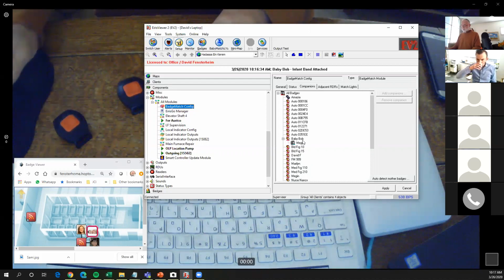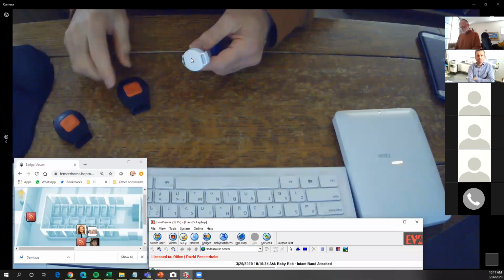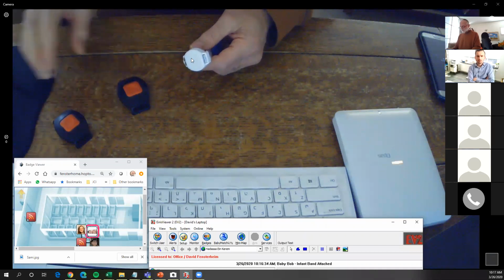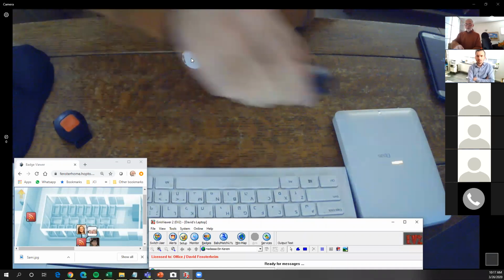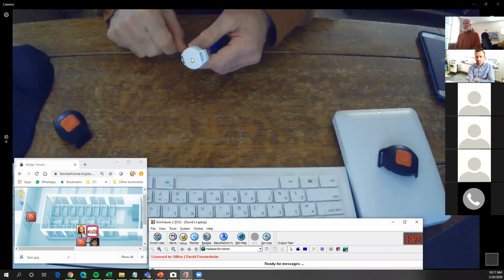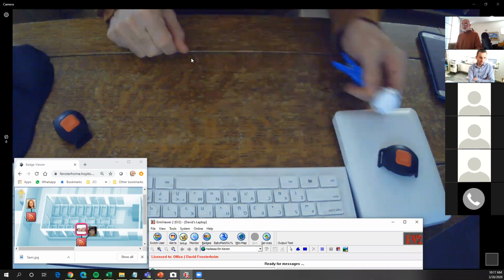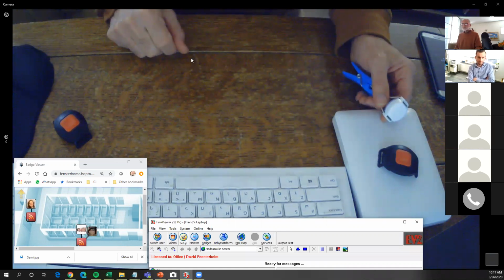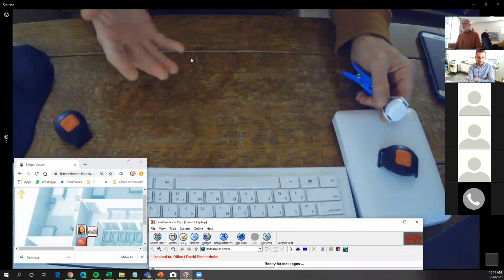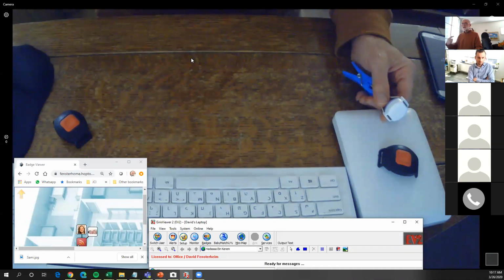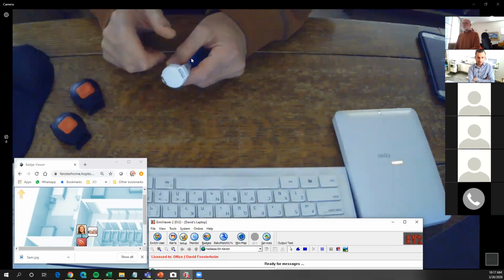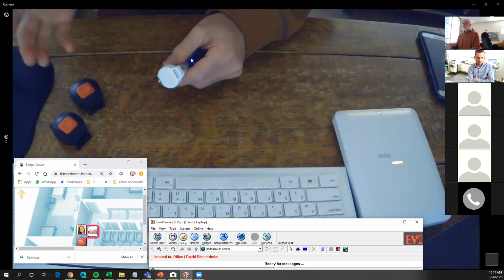So now, not only is the mother tag programmed into this baby tag for the purpose of local matching, in other words, no need for Omni, but if now I put Mom at the exit, and now I move the baby to the exit, I don't get an alarm because we have an escort, now that's because we have the Omni matching.